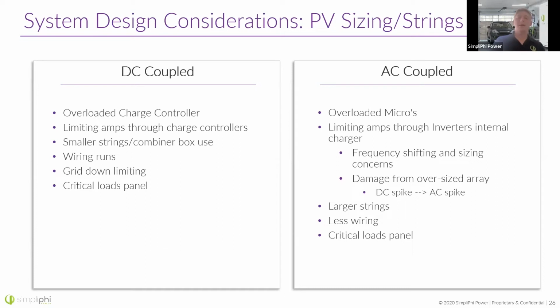Another thing to keep in mind here, so we talked about frequency shifting and the AC coupled array disconnecting from the battery bank. So if you've got a very small battery bank and a very large PV array, and that PV array is selling power to the grid, full power, 10 kilowatts to the grid, let's say. And then all of a sudden the grid disconnects. So in that 1 second, a small portion of a second even, that it takes the microinverters to stop producing such a large amount of power, they have to send it somewhere. And it goes to the battery bank because there's nowhere else to send it. What that causes is a DC voltage spike of these battery banks.